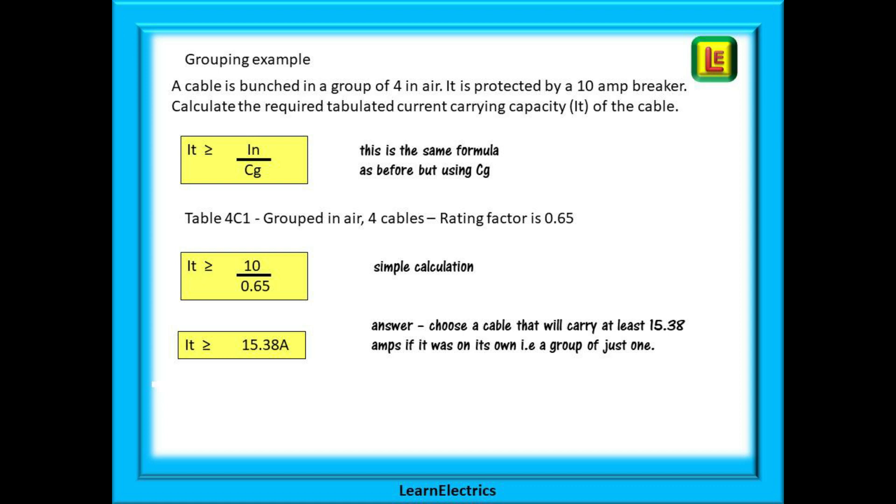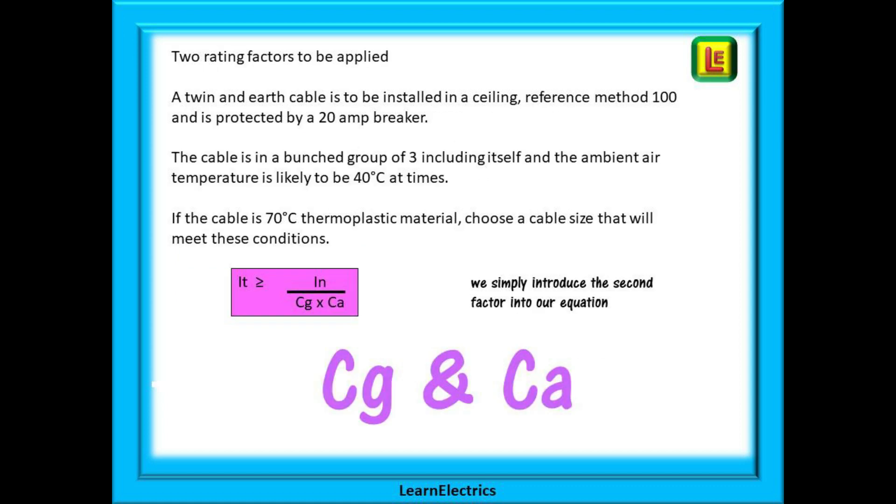And what does this tell us? In order to carry 10 amps in a group of 4 cables your cable must be able to carry 15.38 amps when it is not in a group or a group of 1 as they call it in the book. Now we can apply two factors. So let's see what happens.